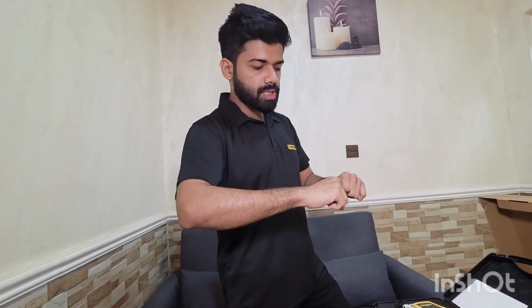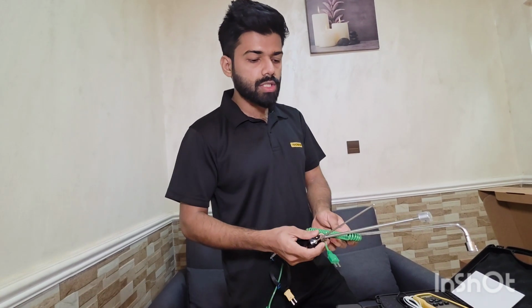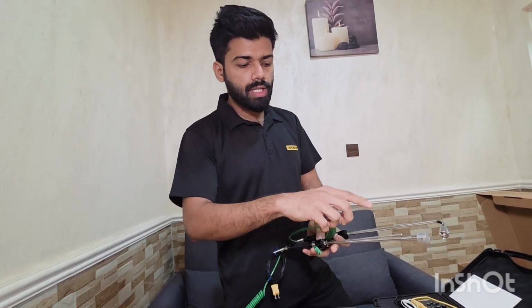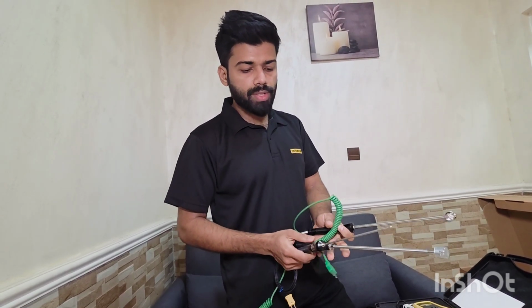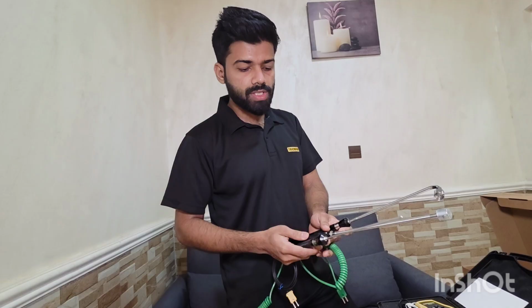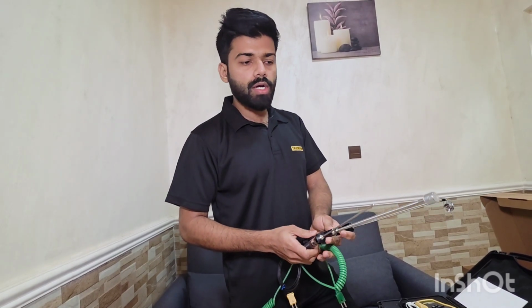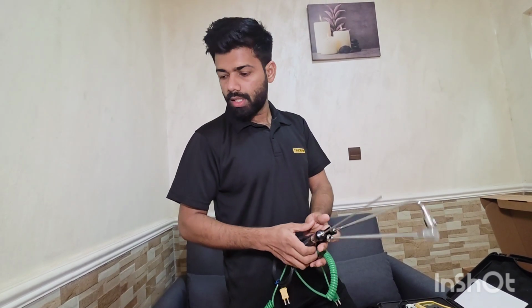Once it is open, it will become a rigid 1 meter probe. That probe can measure 1100 degrees Celsius at the tip part, not at the handle part, because the handle is not capable enough to handle 1100 degrees. So based on the construction of the probe, the safest temperature range for measuring is recommended.